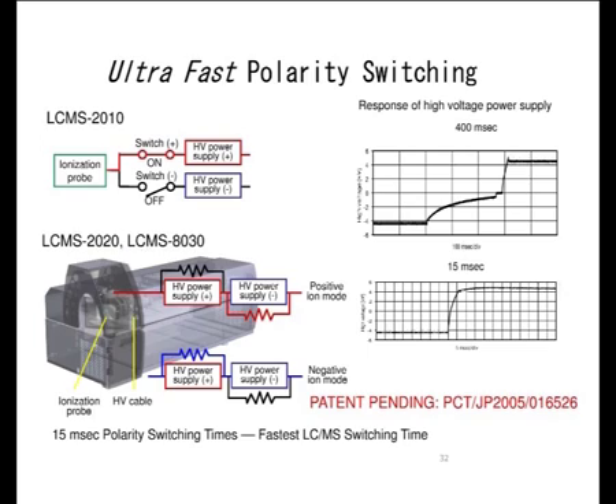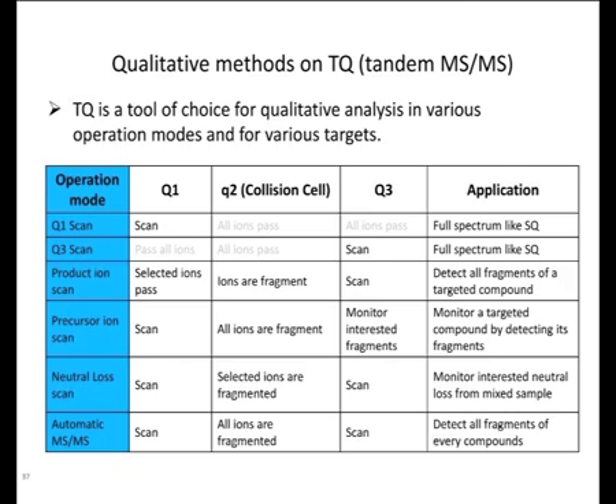Okay, therefore you require the polarity switching time to be very fast, so that you can analyze both the positive and negative modes simultaneously and detect the data. In the Q1 scan, you are scanning all the masses in the first quadrupole, while the second and third quadrupoles act as ion guides. That means they are on RF voltage only, so the triple quadrupole works as a single quadrupole. You only have to detect all the ions generated by the interface.